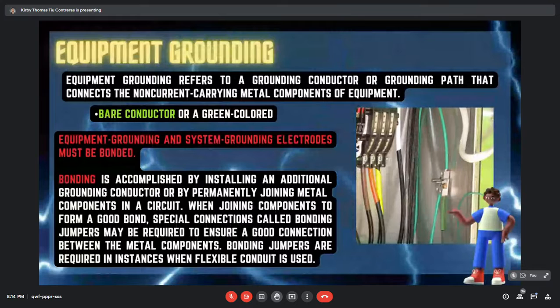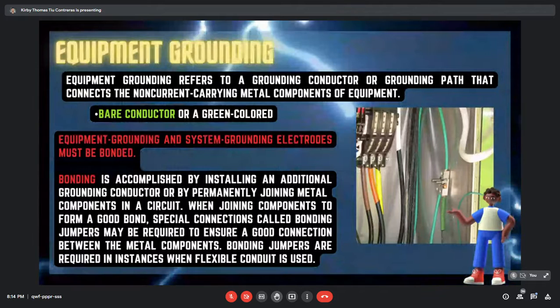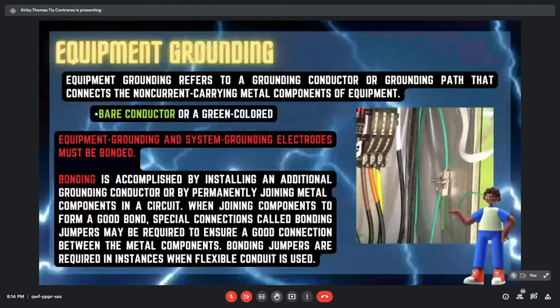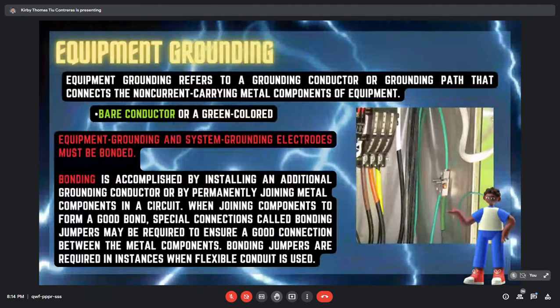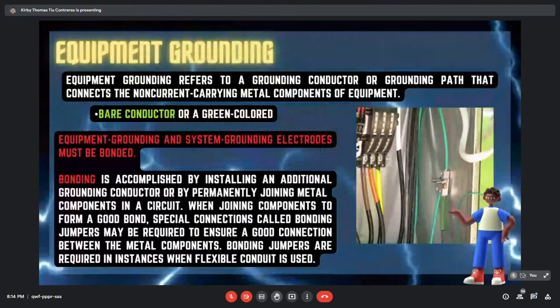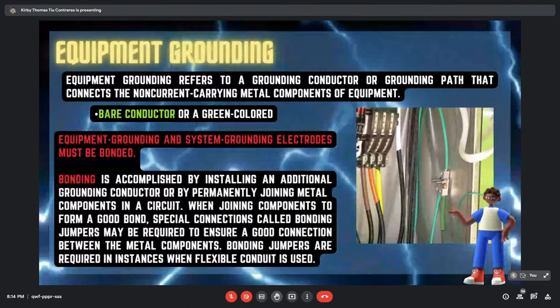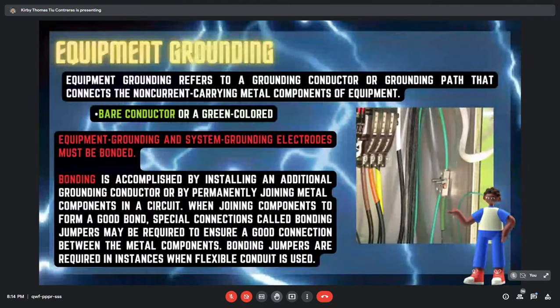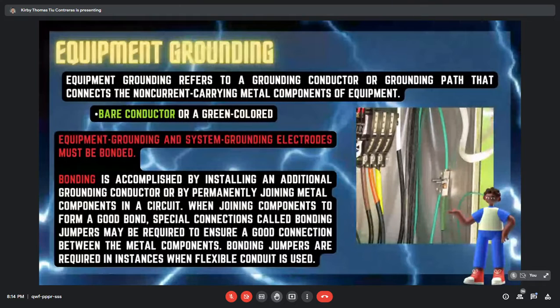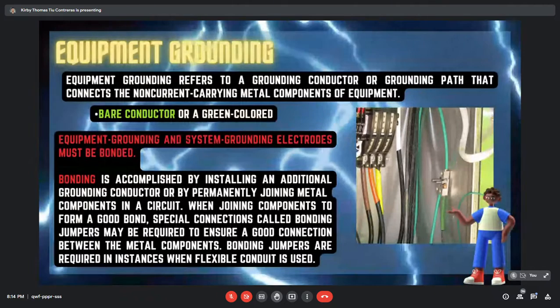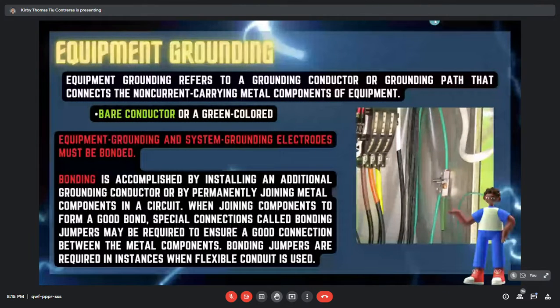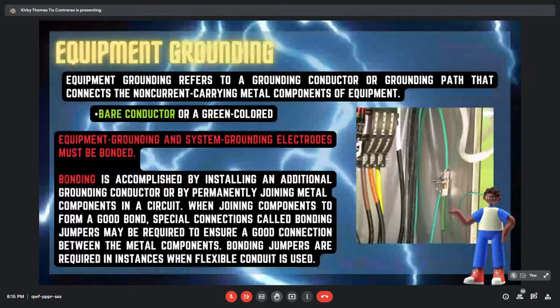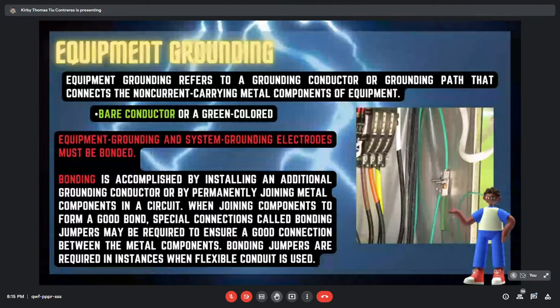So moving on, equipment grounding and the system grounding electrode must be bonded. Bonding is accomplished by installing an additional grounding conductor or permanently joining metal components in the circuit. When joining components to form a good bond, special connections called bonding jumpers may be required to ensure a good connection between the metal components. Bonding jumpers are required when flexible conduit is used.